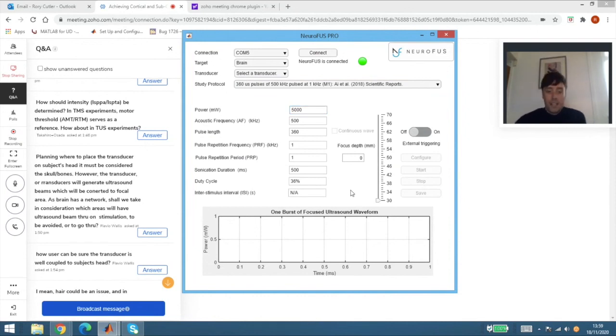In the literature, people tend to report the pulse repetition frequency, but on the technical side, what the device needs to know is the pulse repetition period. So this software handles the pulse repetition frequency to pulse repetition period conversion for you, so you don't have to make calculations manually and risk errors. It also calculates the duty cycle for you. In this case, the pulse length was 360 microseconds, and the pulse repetition period is 1 millisecond.